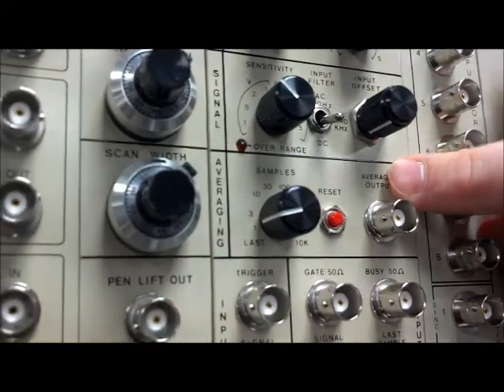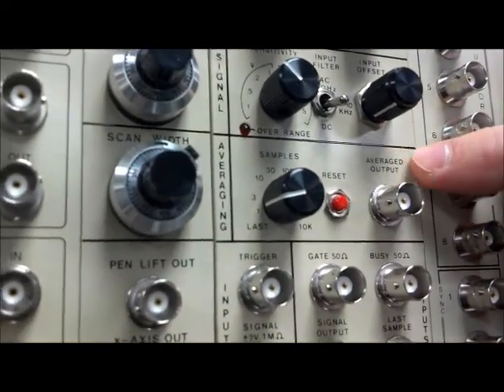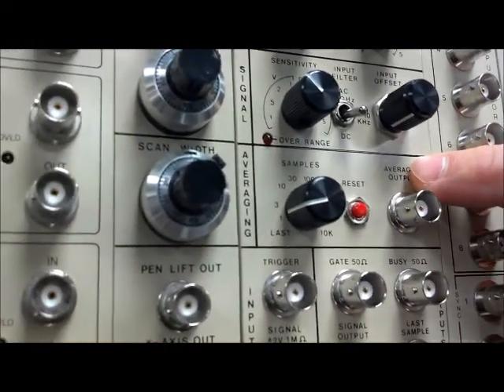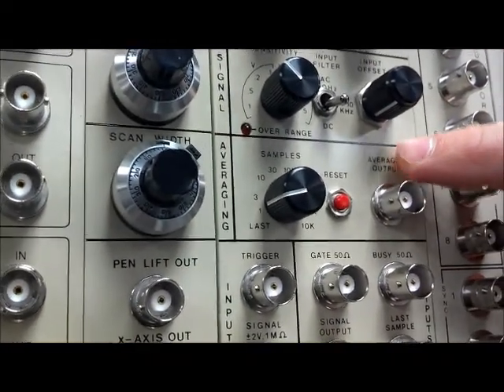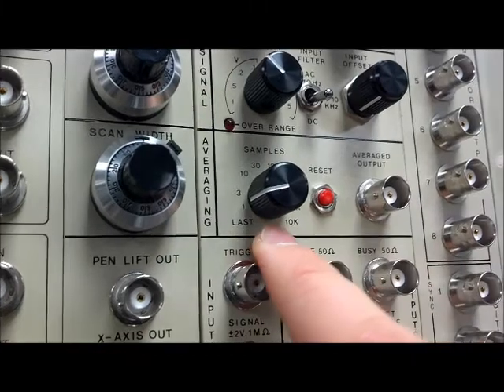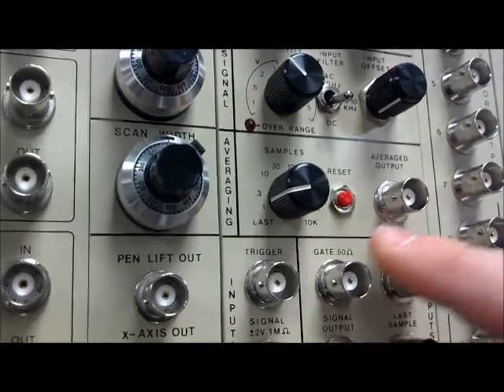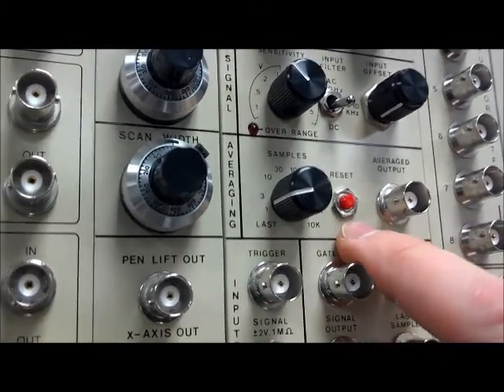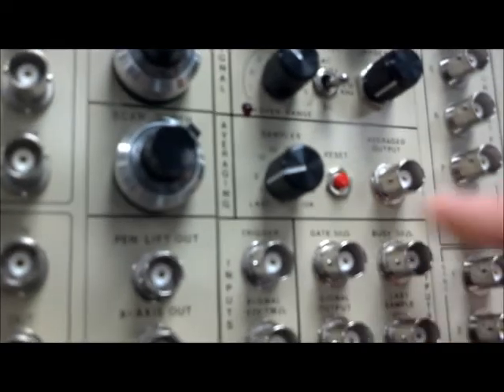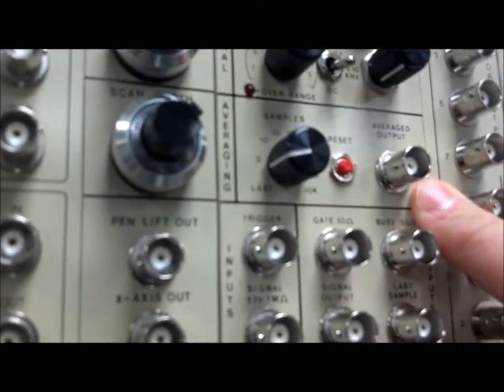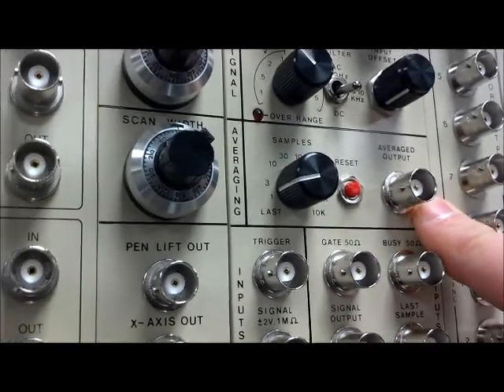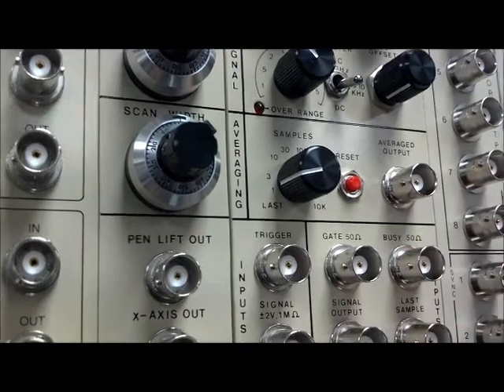The next section is the averaging section. This is an exponential moving average that the user is allowed to set the samples for. The reset button allows for the resetting of this average output. The average output BNC gives the output to the user through a BNC cable.